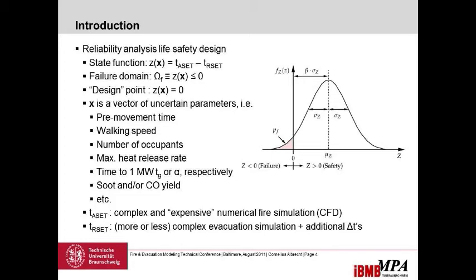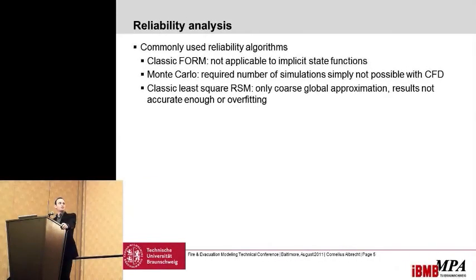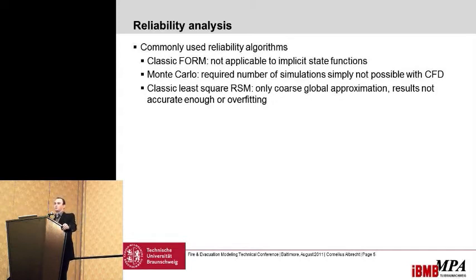For the required safe egress time, we use more or less complex evacuation simulations, and we also have additional delta Ts like the warning time and pre-movement times. Looking at reliability analysis algorithms, many can't be used here: the classical FORM algorithm is not applicable because it needs explicit limit state functions, and what we have is implicit because we utilize numerical tools. Monte Carlo is not applicable because we need a high number of simulation runs, which is not feasible with CFD.